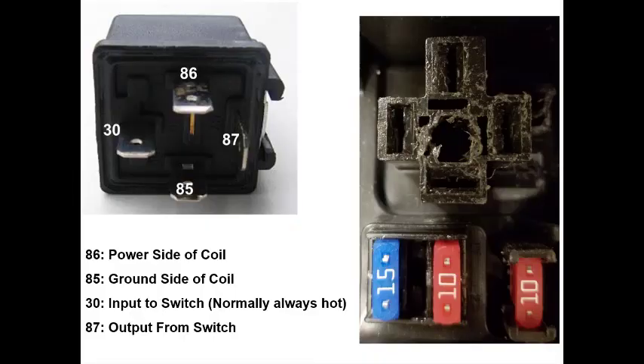Now that we have fully reviewed what the pins on the relay correspond to, we can now test the terminals inside of the relay socket. These socket terminals are only identifiable by matching up how the relay inserts into the socket. Many relays, with the exception of a few, have offset pins, making it so they only insert one way into the socket itself. Once you have referred to the wiring diagram and established which pins match up with the socket terminals, you can test the circuits based on what they should have for powers and grounds.